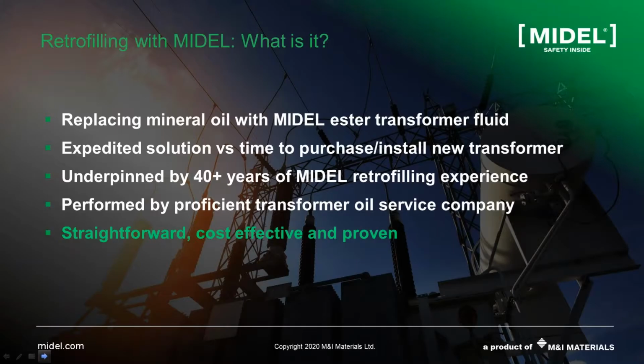So what is retrofilling? Our definition is to simply replace the existing mineral oil in your transformers with MIDEL. There is no need to wait for new equipment lead times or the burden of complicated project construction phases. It can be done on site in a time-efficient manner.